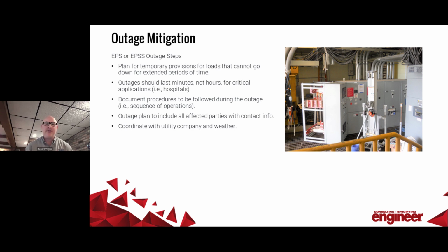They required letters to the Department of Public Health because this was a hospital, and lots of plans with all the departments. Inevitably, your client's going to lose money because they're going to have to go on trauma bypass as a hospital, and shut down processes as a facility. So we want to make sure that this is not a just replace in place scenario, and it's means and methods. The engineer of record and the designers have to plan early and often and communicate with the client all the expectations necessary to transfer from permanent to temporary and back again.